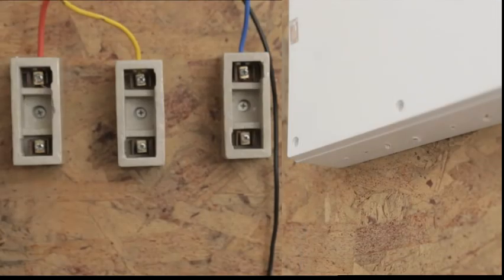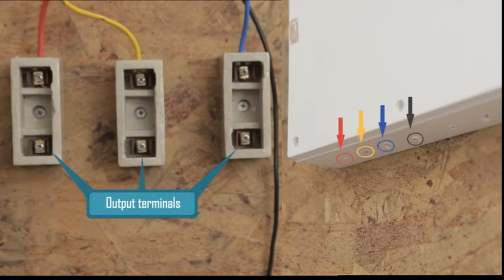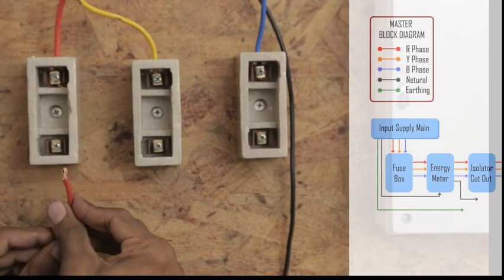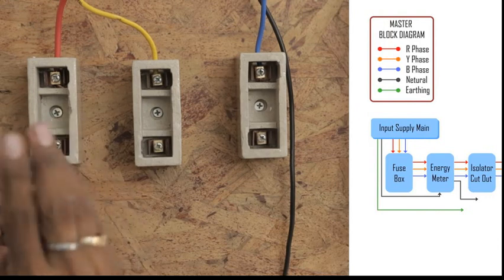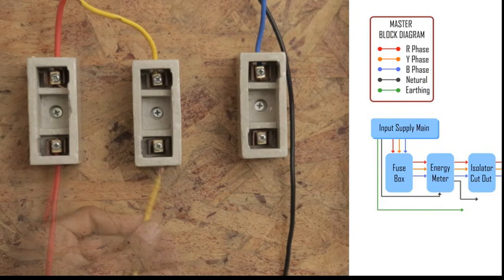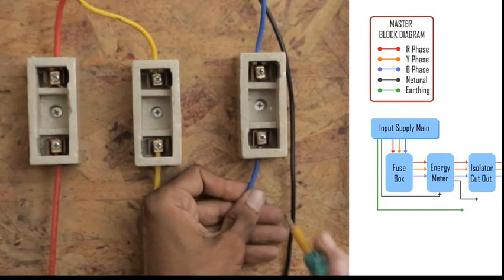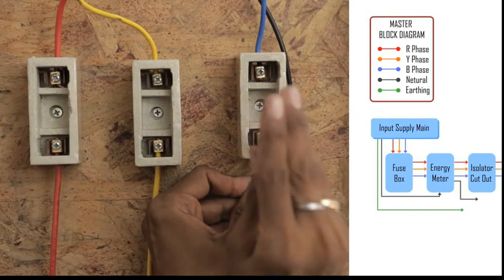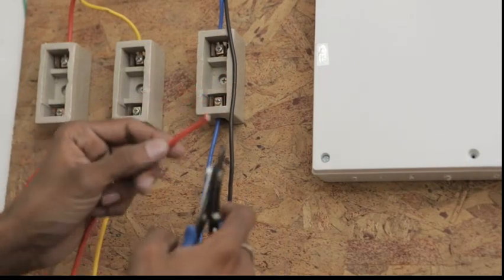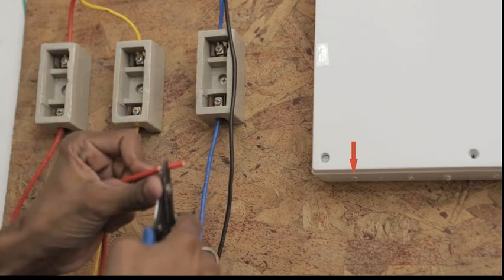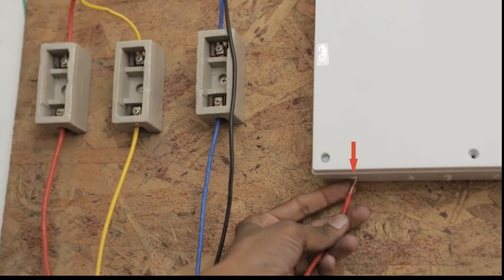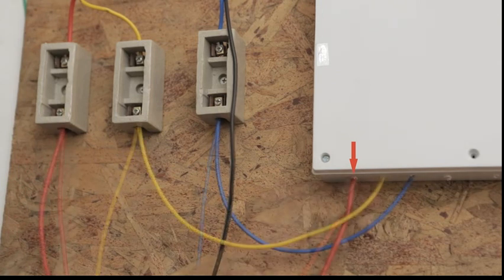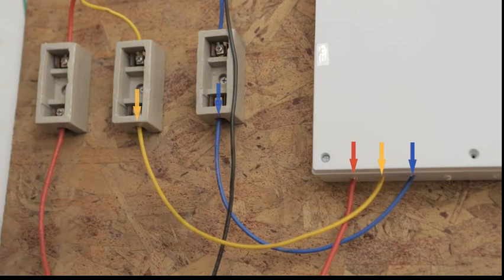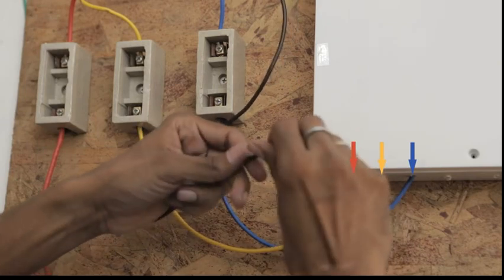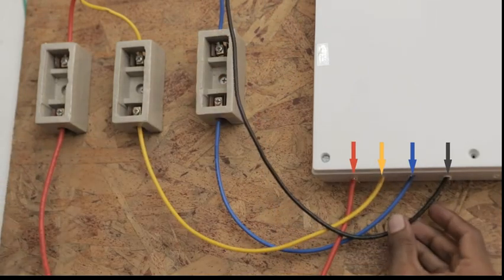Next, connect the output terminals of the fuse box to the input terminals of the energy meter. Start by inserting the red wire into the R phase fuse output. Similarly, insert the yellow and the blue wires into the Y and the B phase fuses output. Connect the R output of the fuse box to the R input of the energy meter. Similarly, connect the Y and the B outputs of the fuse boxes to the Y and the B inputs of the energy meter. Then take the black neutral wire from the input mains and connect it to the input neutral terminal of the energy meter.